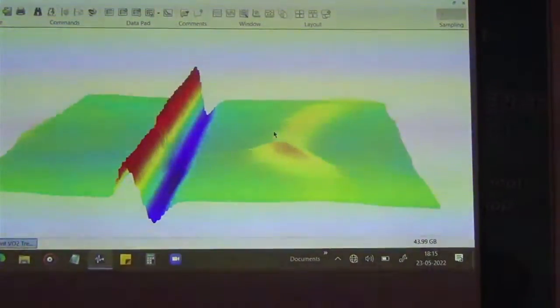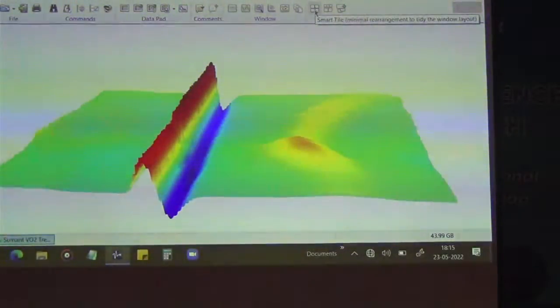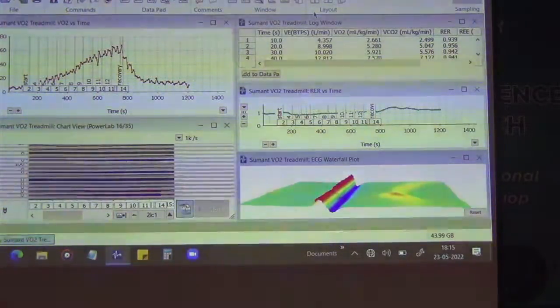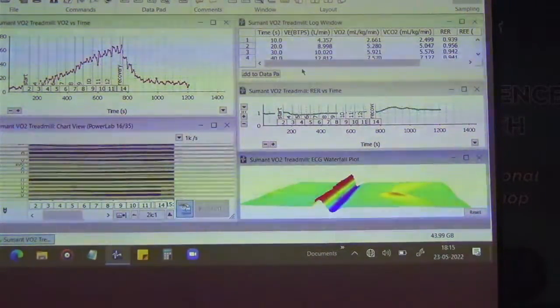Right now we are breathing and feeding, but here we feed gas with a known percentage of carbon dioxide and oxygen, and we calibrate the machine to 15.3 oxygen and 5% carbon dioxide. So calibration is over, and whatever we breathe out, values come according to this calibration. We have to do it now and then, otherwise we won't get it. That is one part, gas calibration.